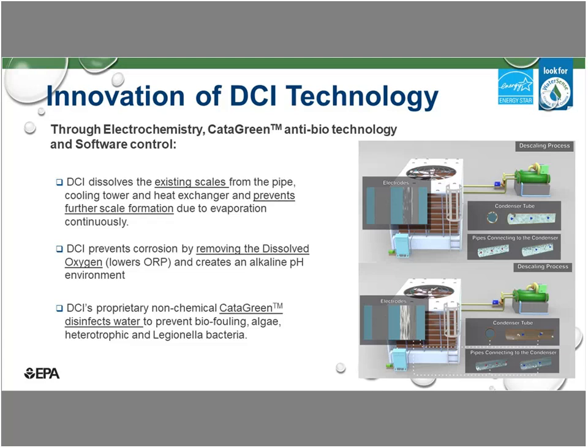Okay, so what DCI does is that we dissolve existing scale from the pipes, the cooling tower, and the heat exchanger, and on top of that, we prevent further scale formation due to the evaporation that happens continuously. The way we are able to dissolve existing scale is like this. On the right side, where my cursor is, this is where our electrode is.